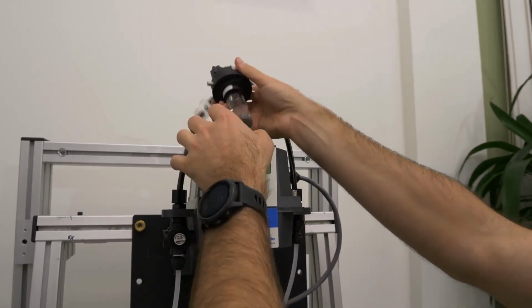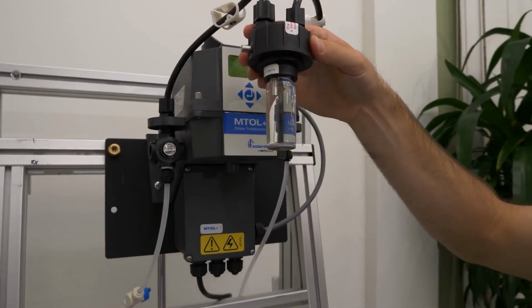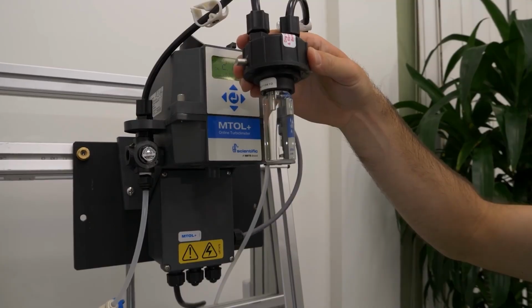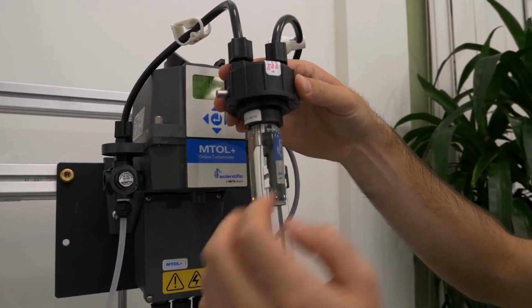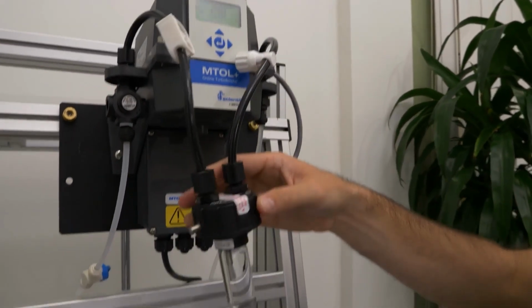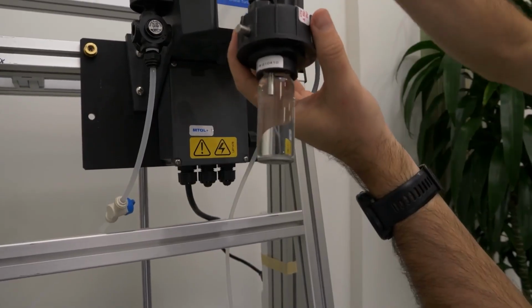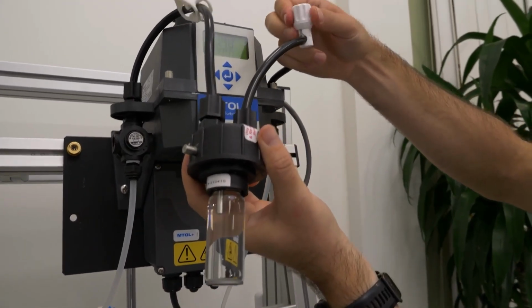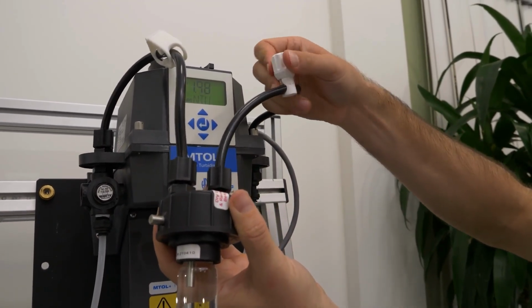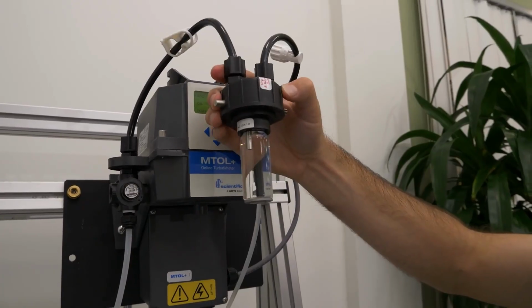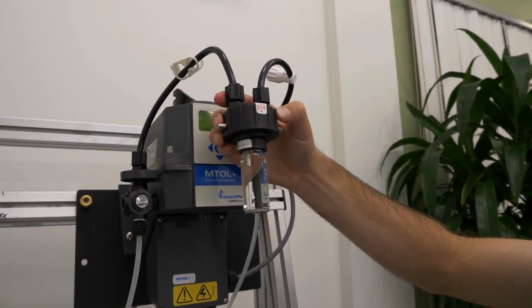Once water is flowing through the cuvette, inspect the cell by removing the flow head from the analyzer without disconnecting any of the plumbing. If there are bubbles forming inside the cuvette, rotate the back pressure valve on the outlet tubing to create more back pressure on the cell and keep the bubbles in solution.